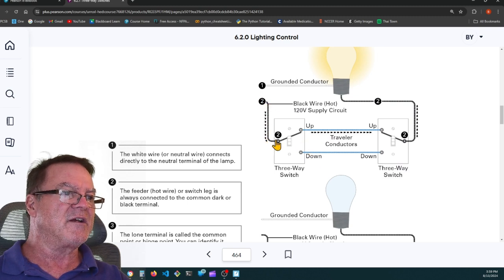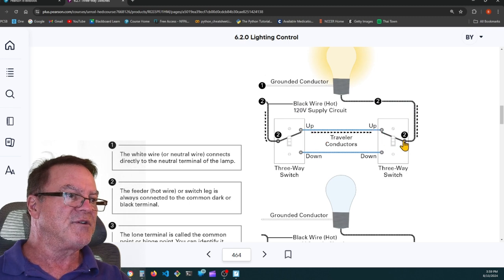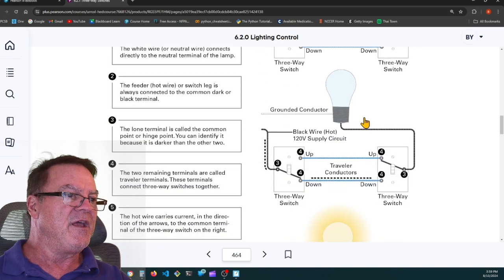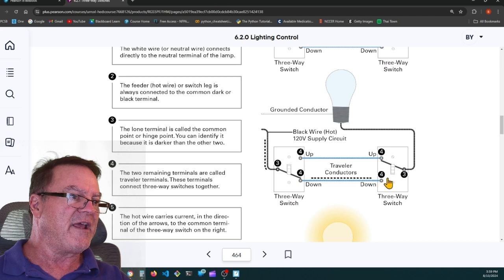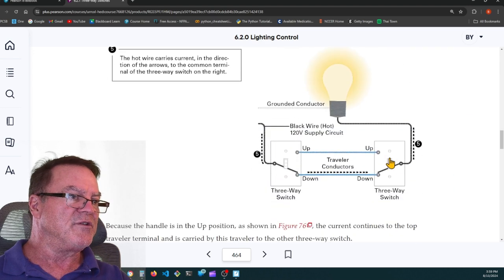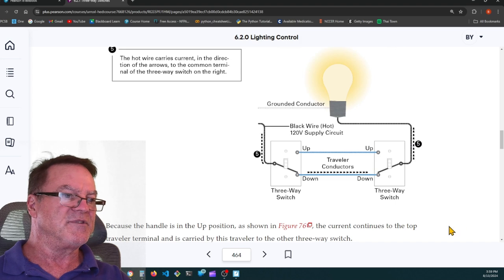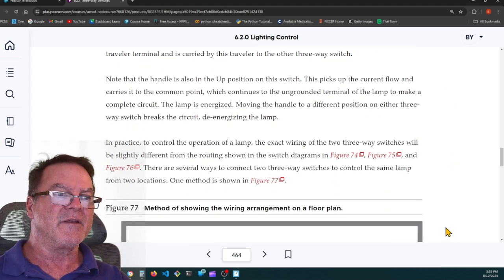So we can see that the hot comes in and goes to one of the commons. You have two travelers running between the two traveler screws. And then the other common is the switch leg going to the light. So that when both of these switches are up, the circuit is made and the light is on. You can turn either one of these switches to the down position, and now there's not a continuous path for current to flow, and the light goes out. But when you turn this switch down again, now the two of them are on the bottom traveler, and there's continuity throughout the system, and the light comes on. Okay, that's how they work.